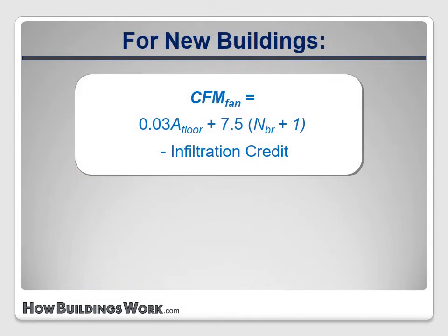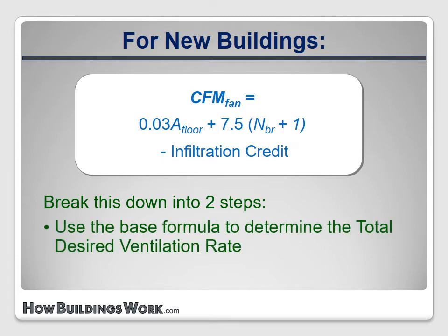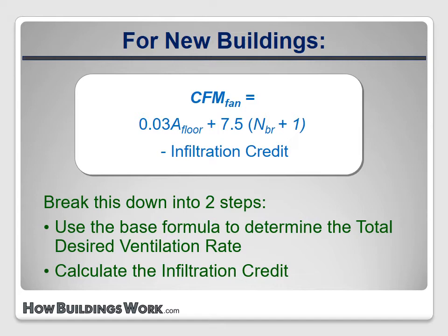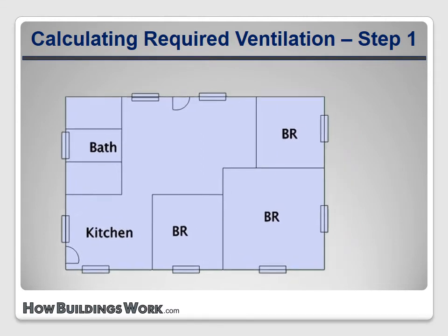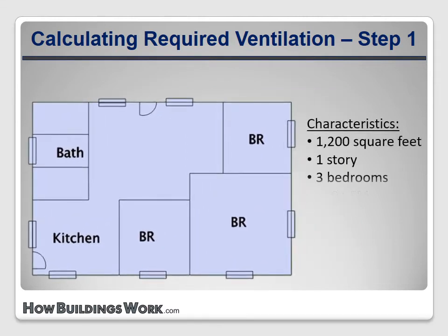Here's the formula. We can break it into two steps: first, we'll calculate the total desired ventilation rate using the base formula, and then we'll calculate the infiltration credit. Let's apply this to a sample house — a simple ranch with three bedrooms and about 1200 square feet of living space, being built in a new subdivision just outside of Trenton, New Jersey. It's a pretty tight house in the New Jersey Energy Star Homes program, so the blower door reading is just 850 CFM at 50 pascals.